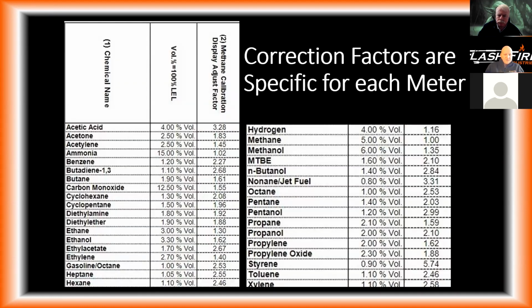So this is a correction factor sheet for a LEL sensor. And again, all this is doing is taking our known gases. So say we're going to an acetone leak. So we have acetone here. This just tells us what the LEL is, so 2.5%. And remember, natural gas is 5%. So this would be more flammable than natural gas. And the correction factor is a number here.